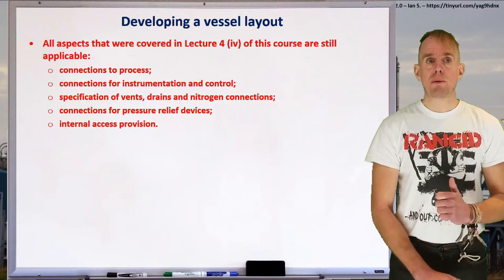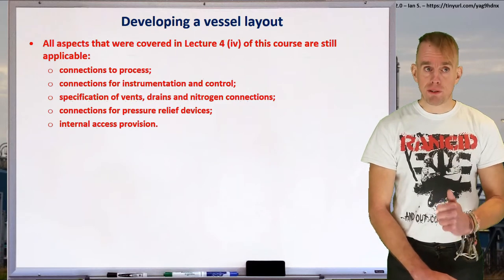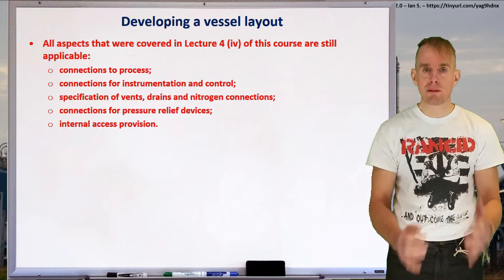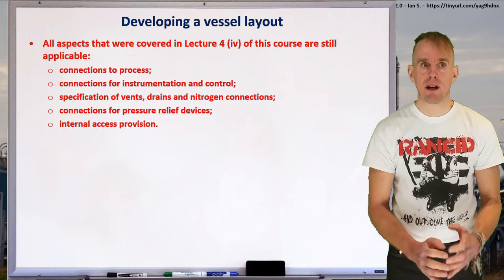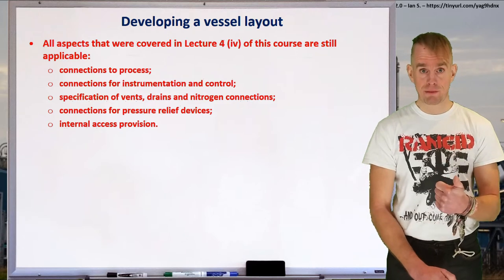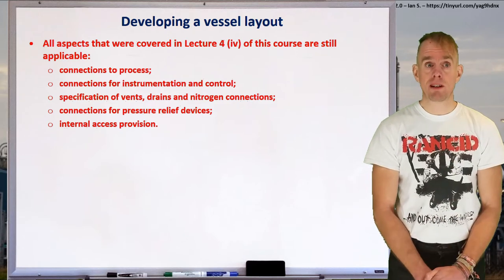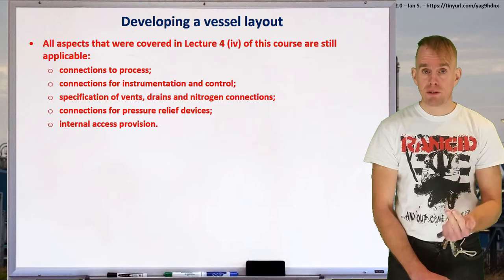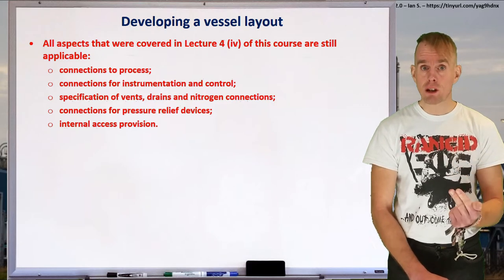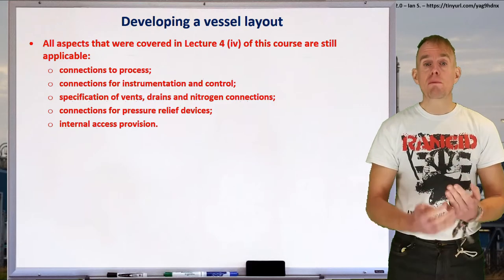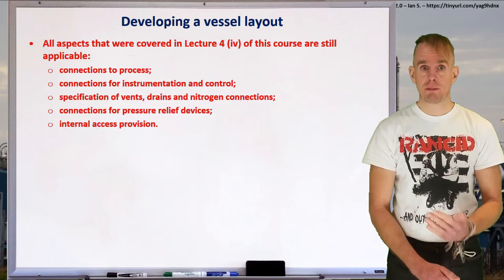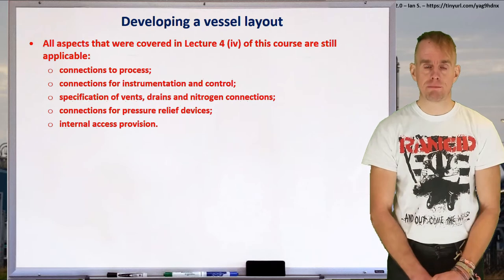A recap of key points from Lecture 4, Part 4 of this course, because they still apply to what we're doing now. When you're developing a vessel layout, don't forget the following: connections to the process; connections for instrumentation and control; the specification of vents, drains, and nitrogen connections; connections for pressure relief devices; and the provision of internal access. This is general to any pressure vessel.